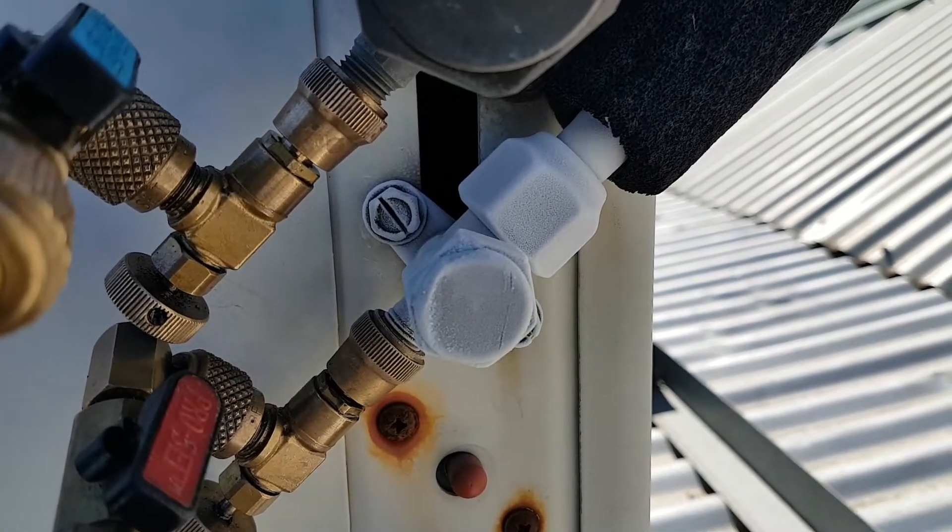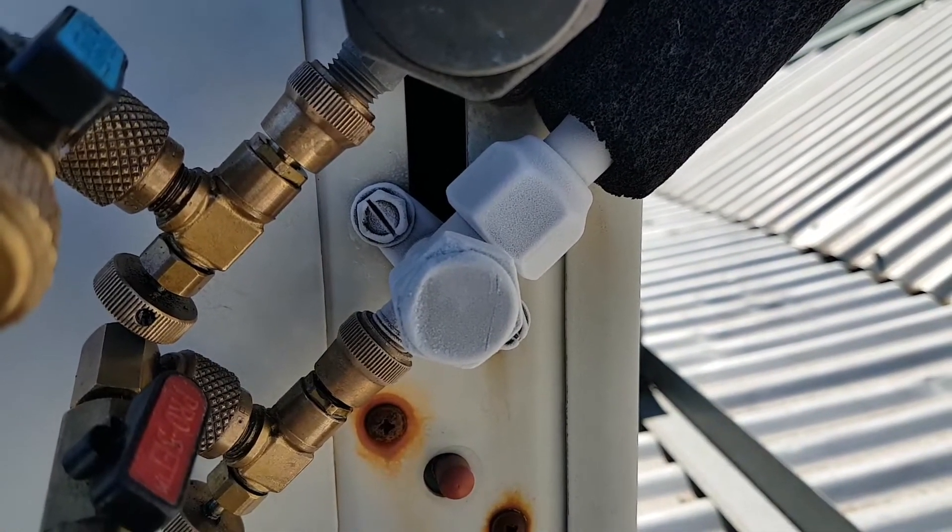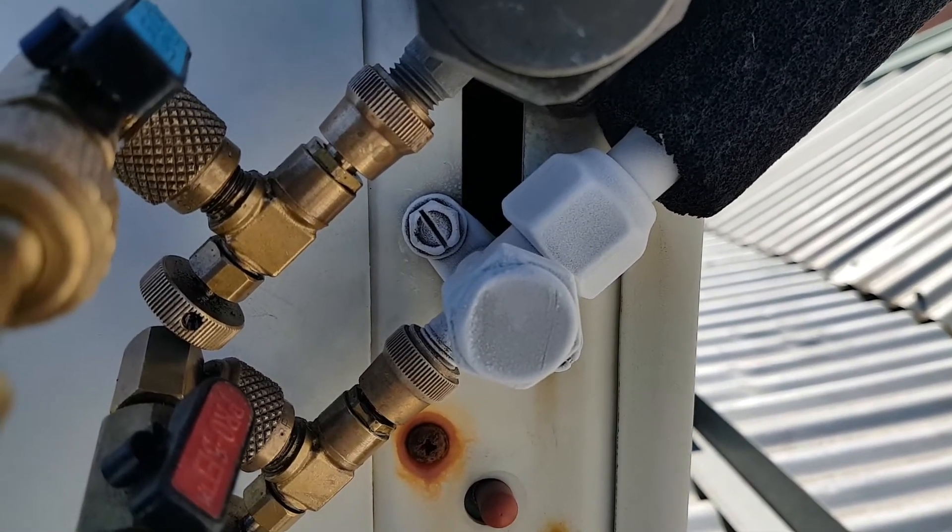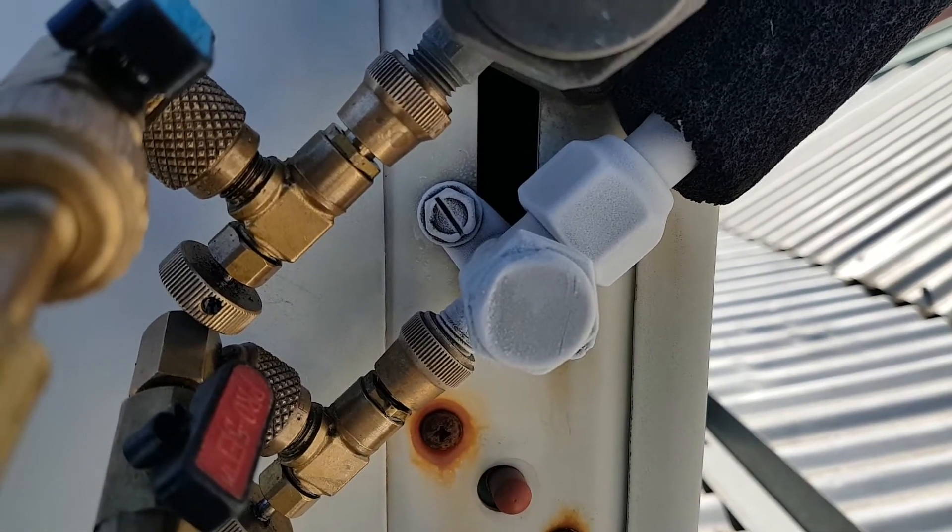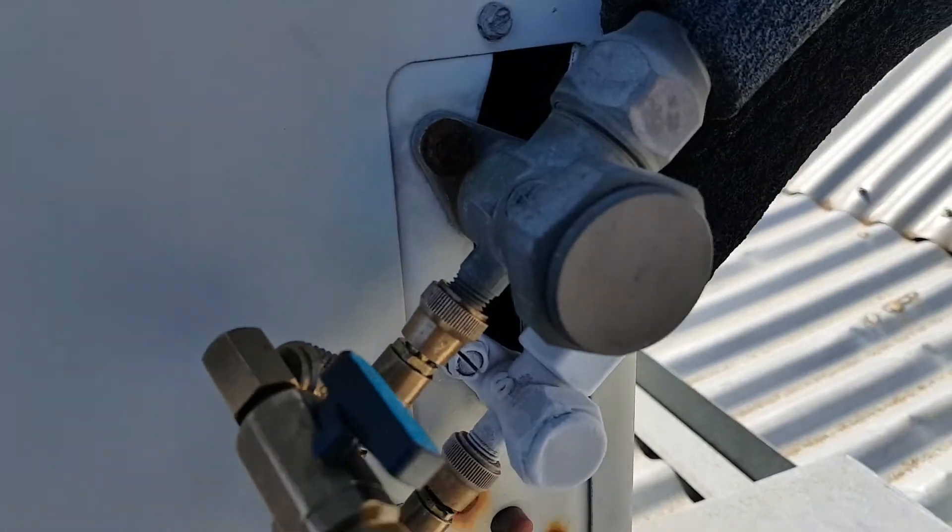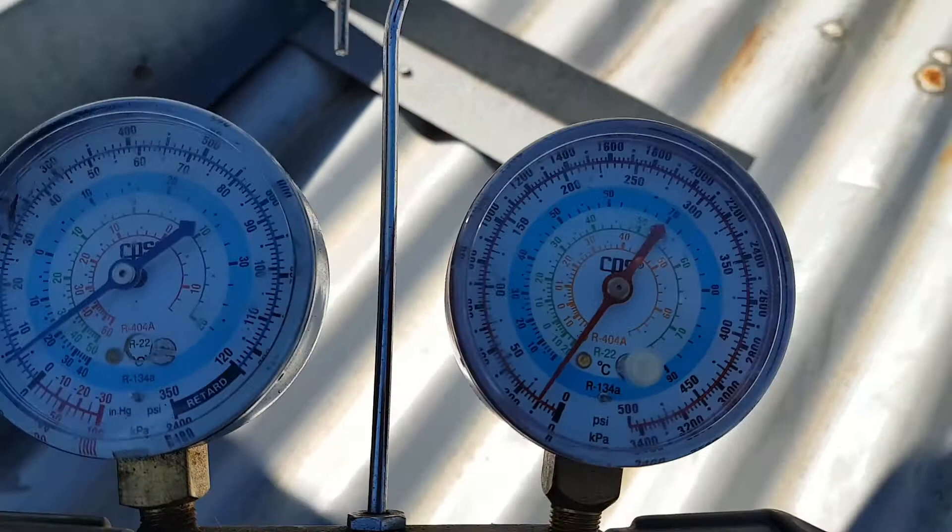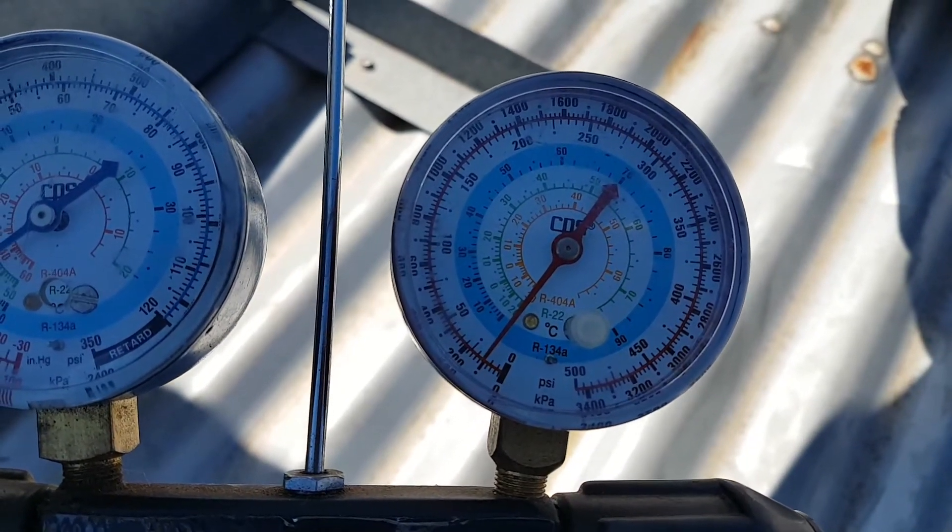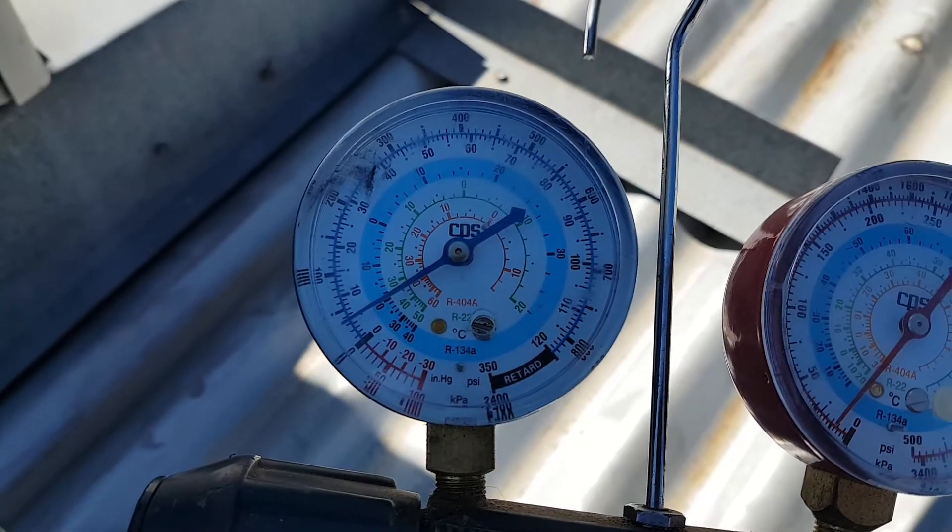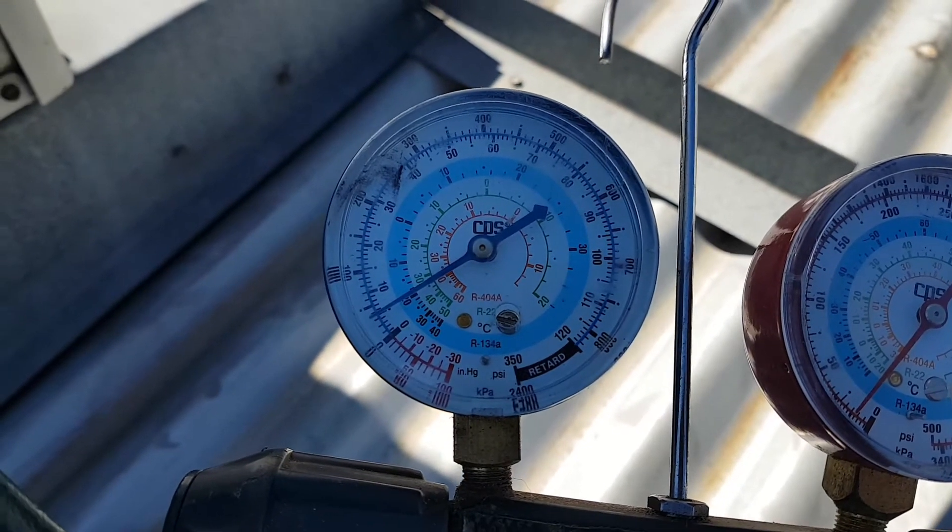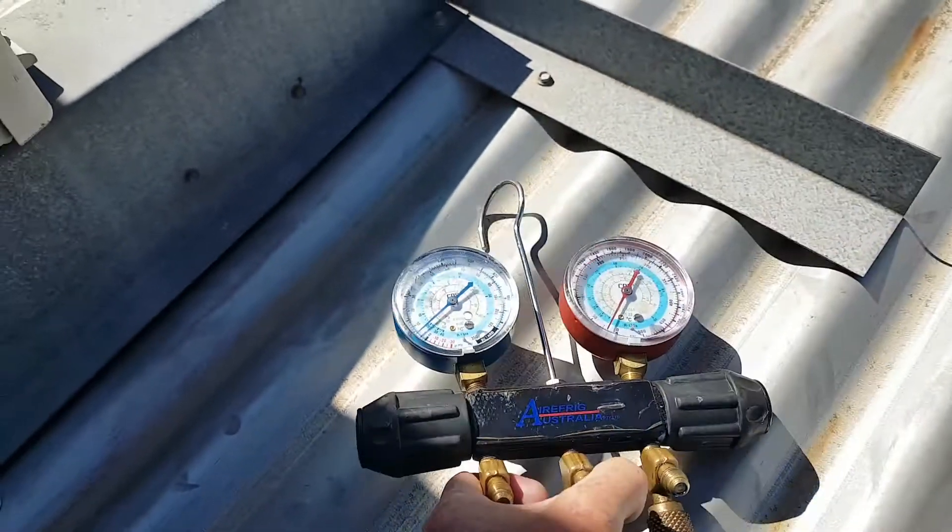What we've got here is a system that's lost most of its refrigerant. The liquid line is icing up, which is a good indicator that it's short of refrigerant. We've got high superheat, low saturated condensing temperature, and very low saturated evaporating temperature. It's an old system, so it doesn't surprise me that it's lost its gas.